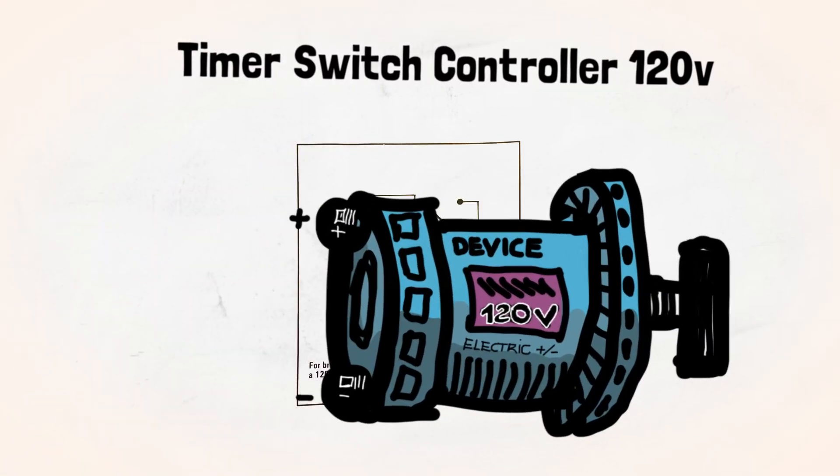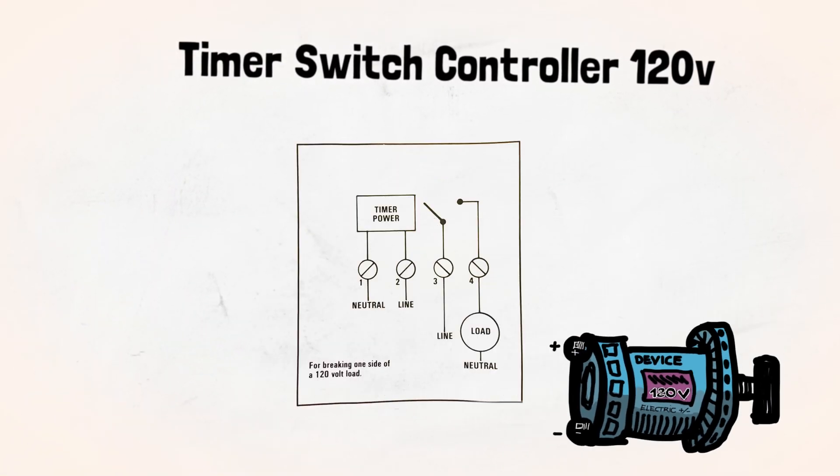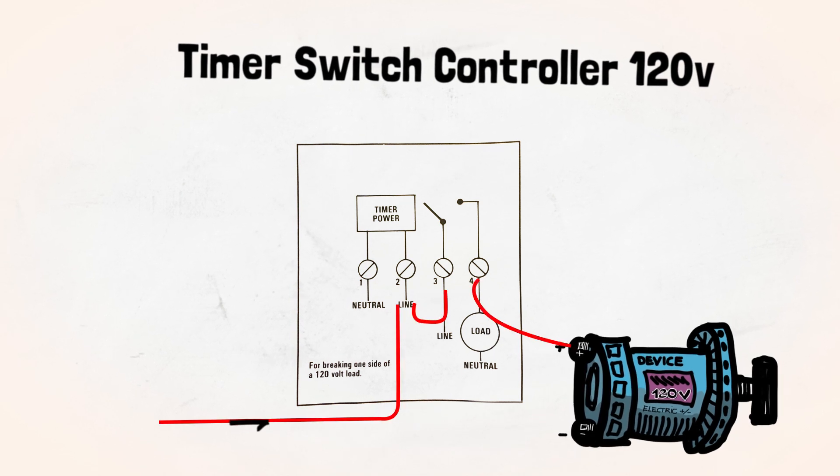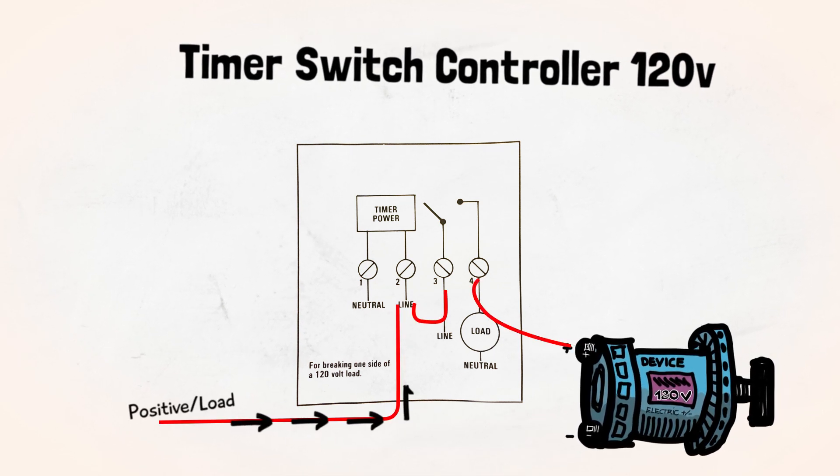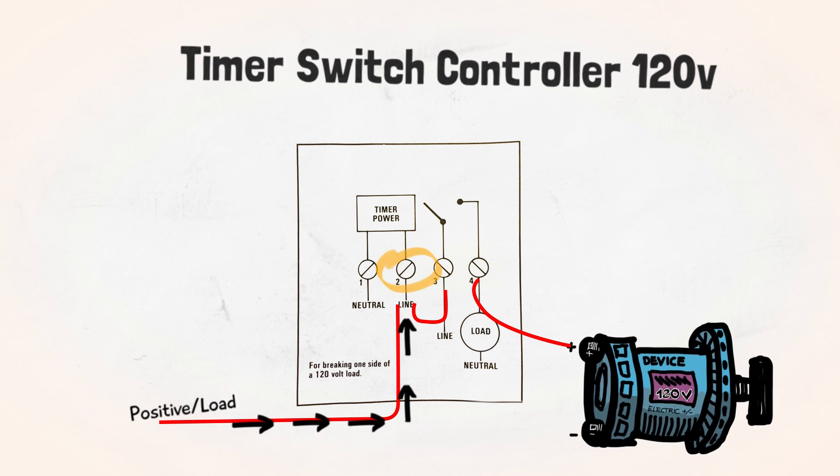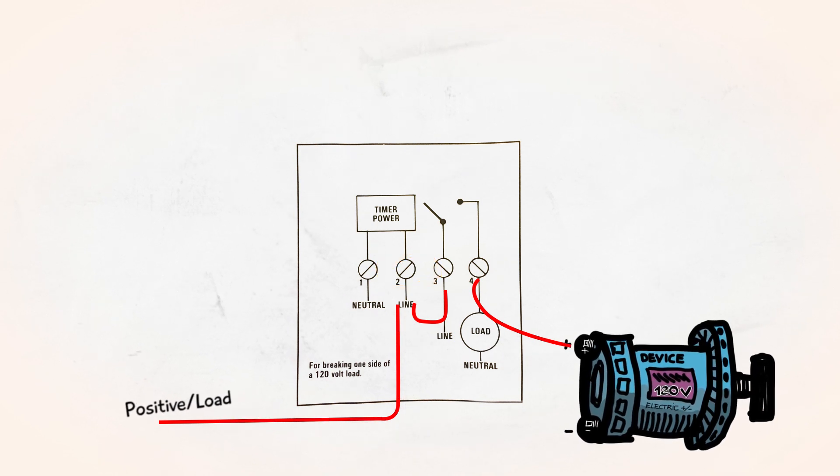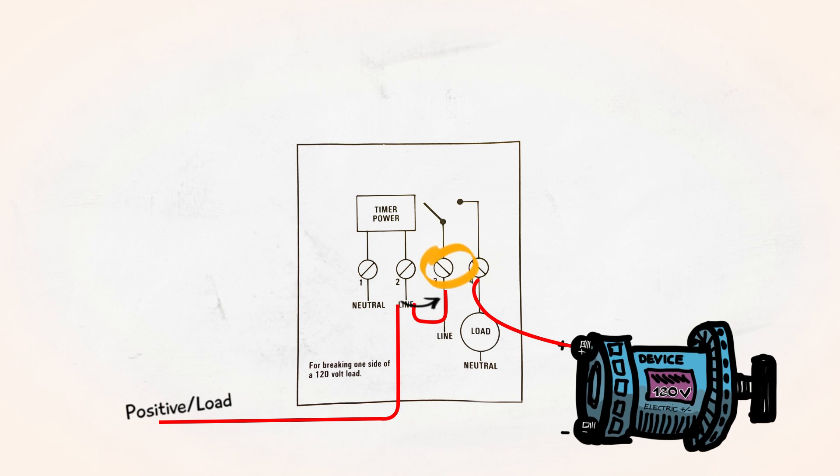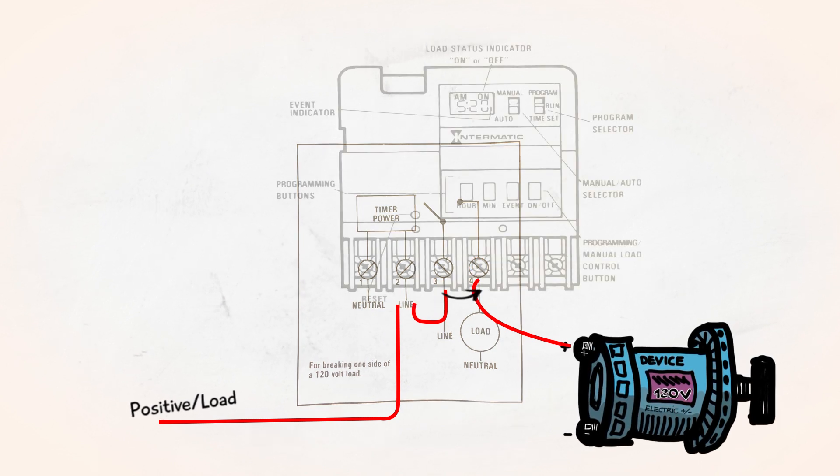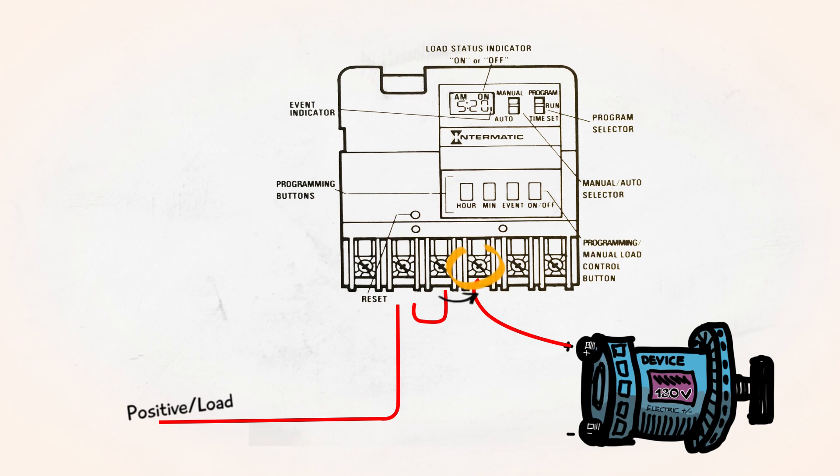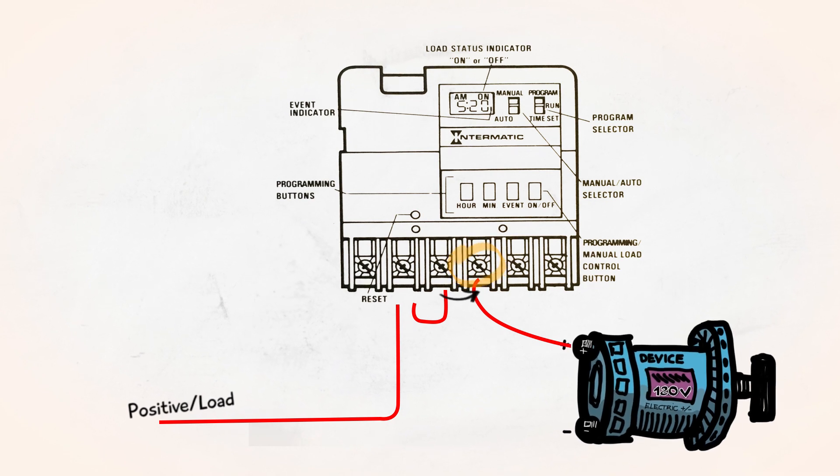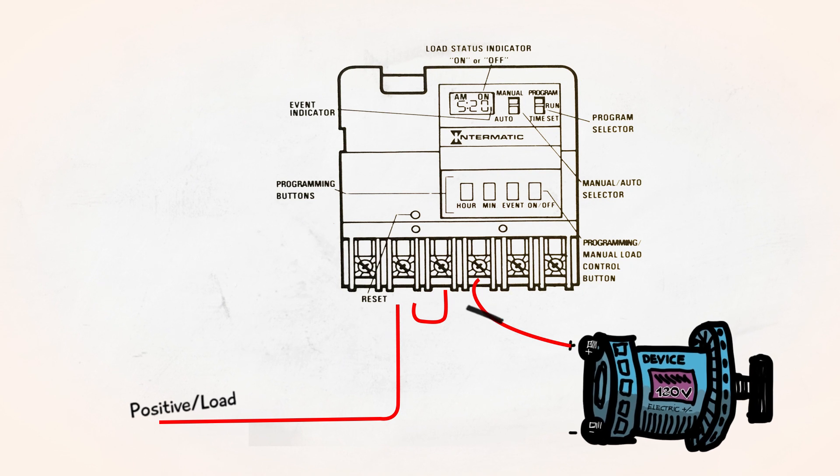For a 120 volt installation the power comes through your hot wire and comes into your timer to terminal 2. From terminal 2 it is bridged into terminal 3 where the power will be hot all the time but the timer will transfer it to terminal 4 every time the timer is turned on. From terminal 4 the power is carried to the device that we are controlling which we call load.